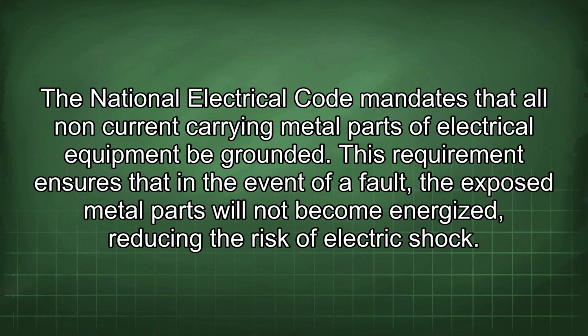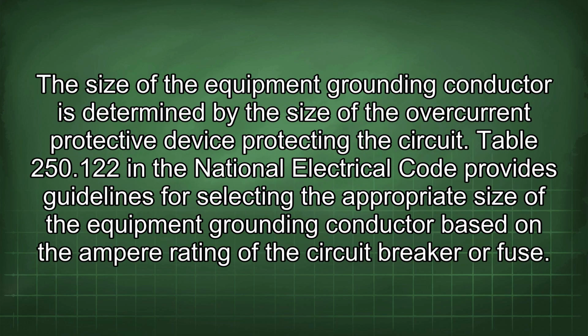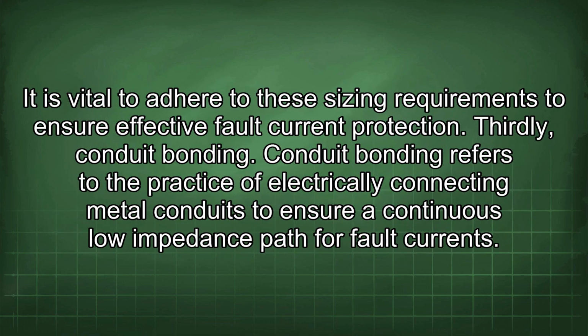The size of the equipment grounding conductor is determined by the size of the overcurrent protective device protecting the circuit. Table 250.122 in the National Electrical Code provides guidelines for selecting the appropriate size of the equipment grounding conductor based on the ampere rating of the circuit breaker or fuse. It is vital to adhere to these sizing requirements to ensure effective fault current protection.